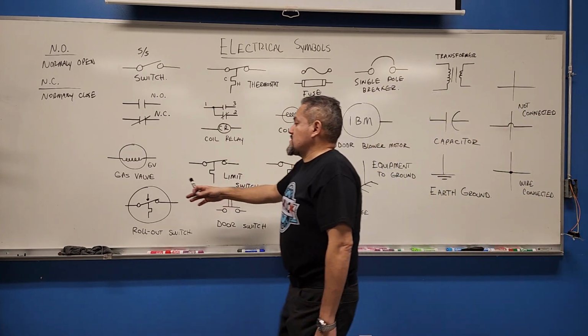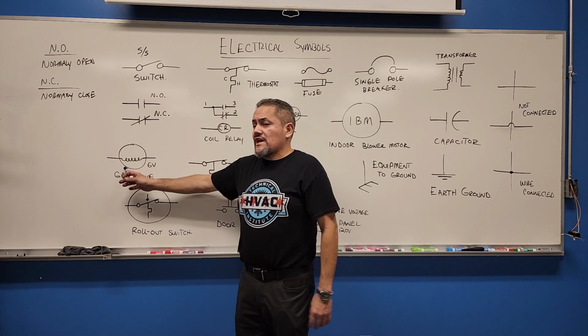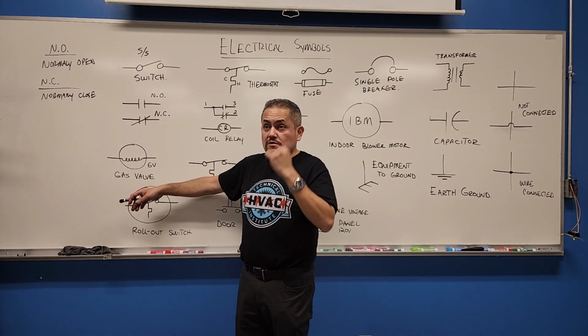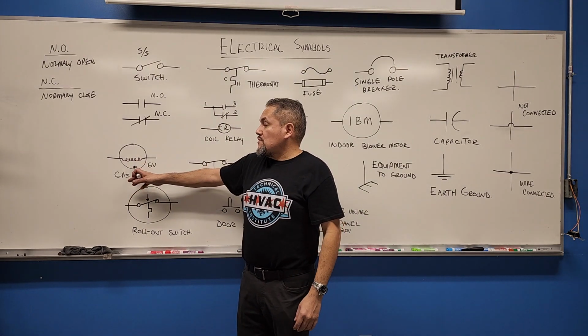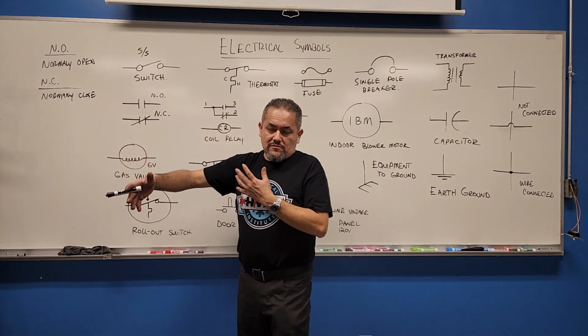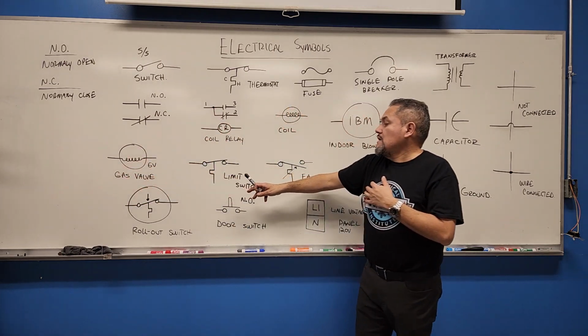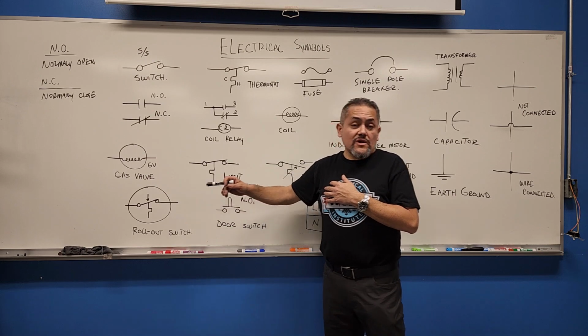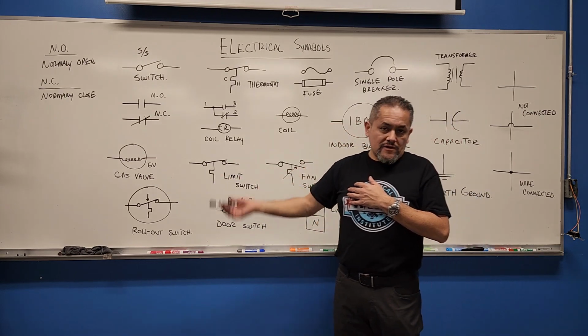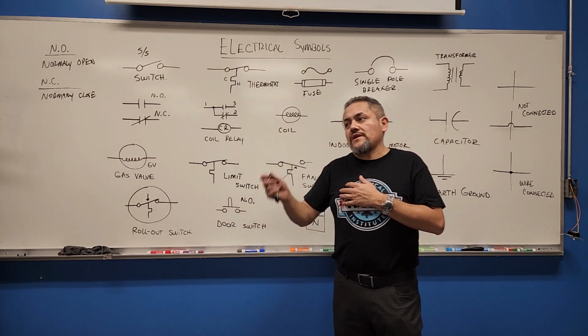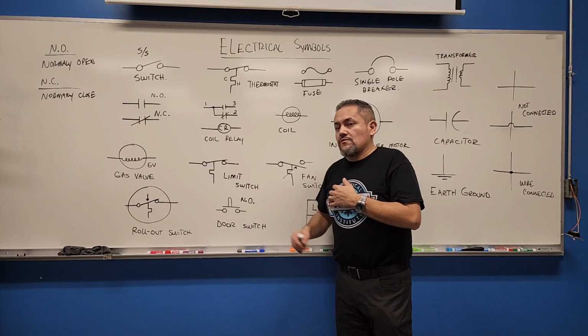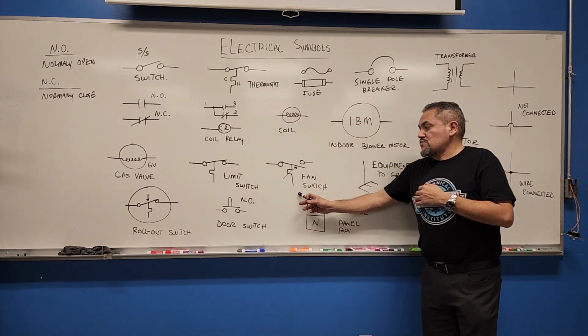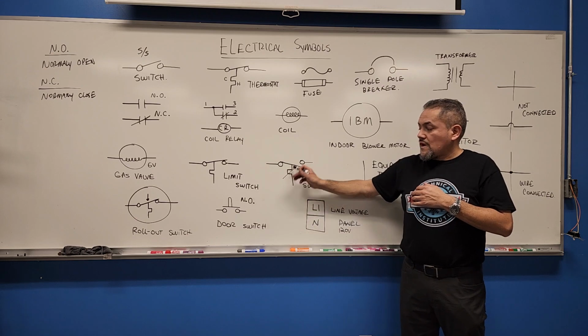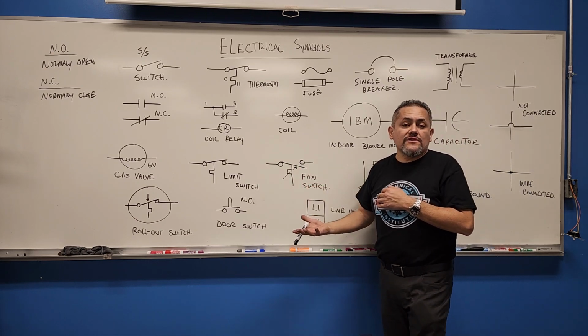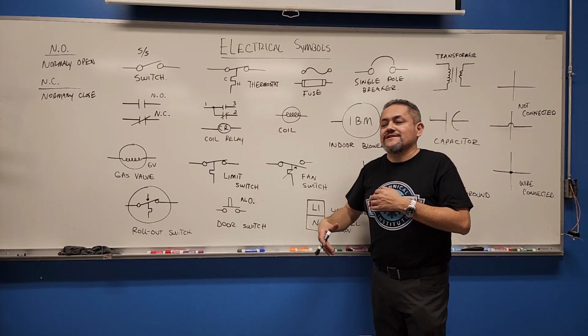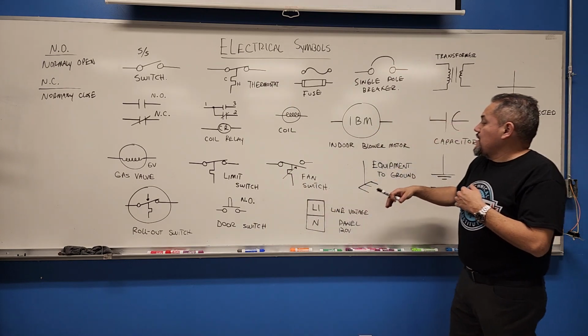And then the next symbol is the gas valve. GV represents the gas valve. This is the one that opens with 24 volts. Once it gets 24 volts, the gas valve opens and releases the gas into the main burners. Gas valve. Limit switch. The limit switch opens the contacts when the temperature goes beyond 200 degrees, depending on the control and how you can adjust it or reset it. Fan switch, normally open, it will close the contacts if the temperature gets to 140 degrees inside the furnace, and this is how you call for fan on.